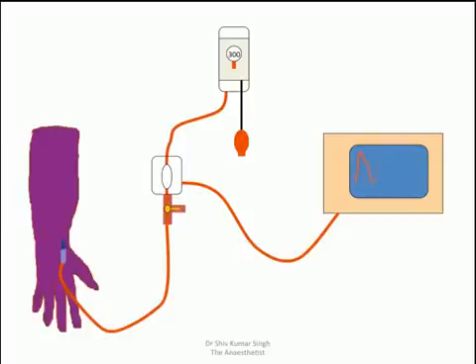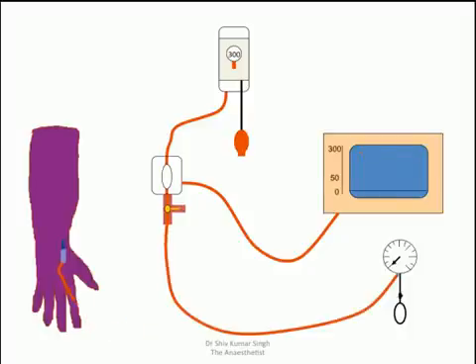Now how do you know that the blood pressure measured by this is accurate or not? So this is where the two point calibration comes in. And this is in addition to the zeroing you do. So first thing you have to do is you have to zero it. So you switch off the arterial line. You disconnect it from your arterial line. And you connect it to a sphygmomanometer. And then you start pumping it to 50 millimeters of mercury. And the graph should show 50 millimeters of mercury. That is if it is accurate. Then you pump it up to 300. And the graph on the screen should show 300 millimeters of mercury.